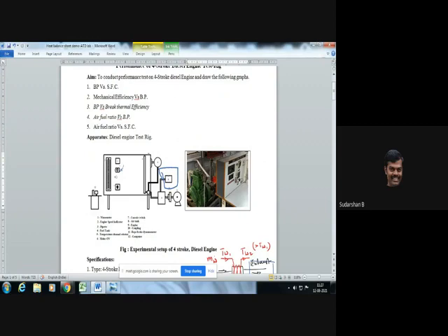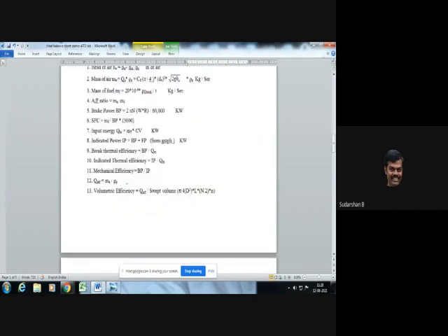Cooling water flow rate will be directly calculated in liters per minute using the discharge meter, not the manometer, as I mentioned earlier. So next you see...